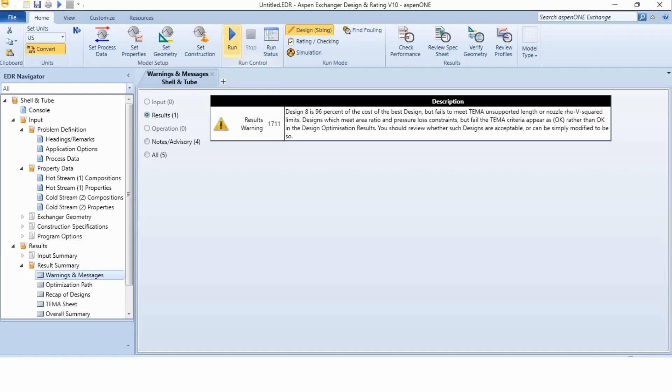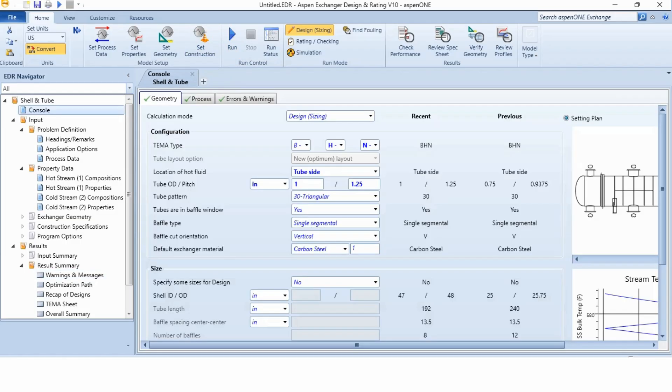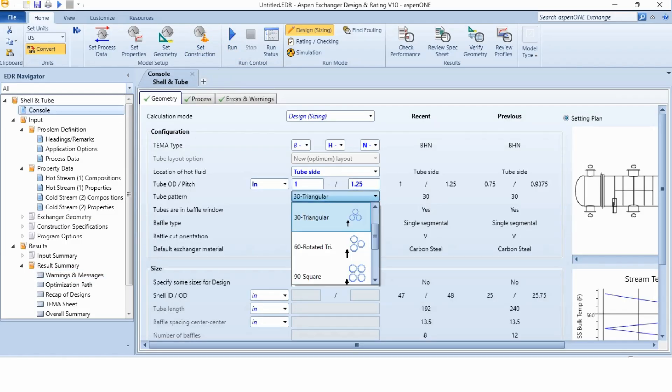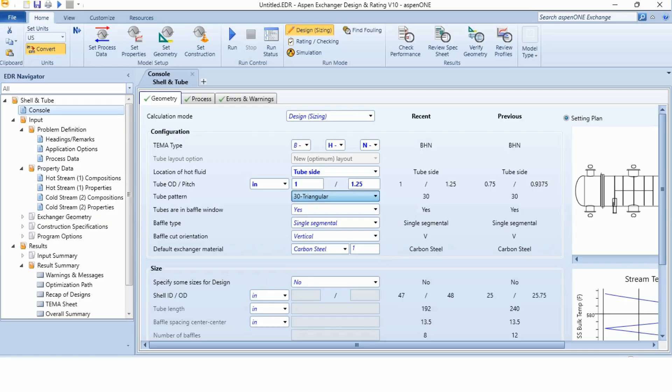Now, the design aid has run the iterations. There are multiple iterations in the system and out of it, out of these design 8 is the best design for it but it is 96% of the cost of the best design. Again, it is not recommended to use it. So, we will go again to the console and the next thing which we can change here is the tube pattern and then we will click on the run again to see whether we can get the required answers or not.